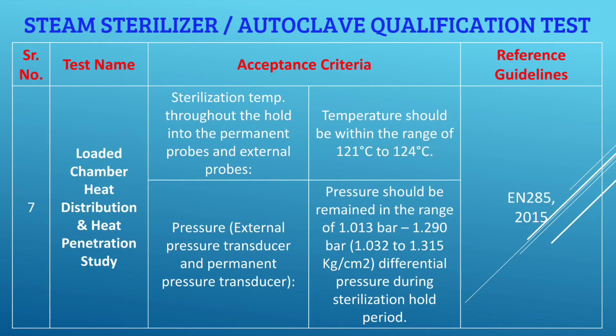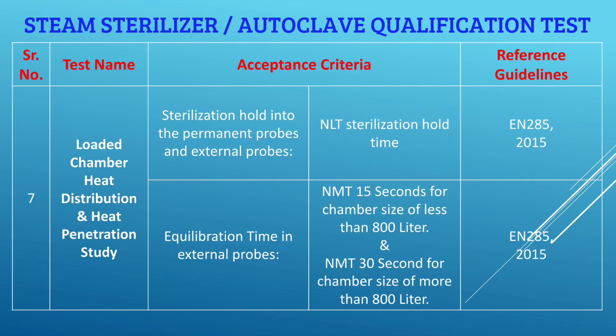For the loaded chamber heat distribution and heat penetration studies, the sterilization temperature throughout the hold in permanent probes and external probes should be 121°C to 124°C — a +3°C band — as given in EN 285:2015. Pressure from external and permanent transducers should remain in the range of 1.013 bar to 1.290 bar based on developmental studies. Sterilization hold time should be not less than the hold time decided during developmental studies.